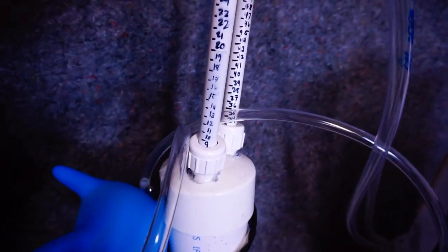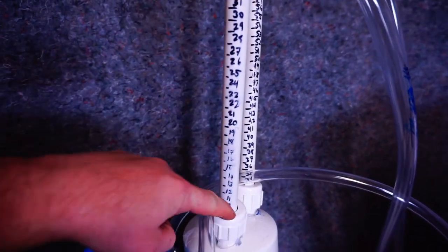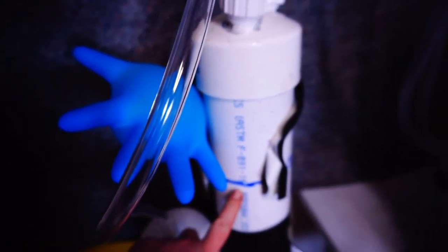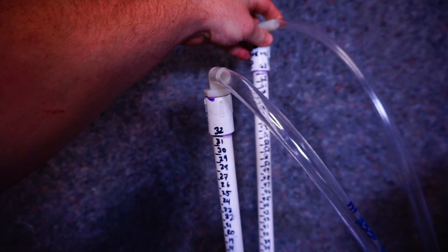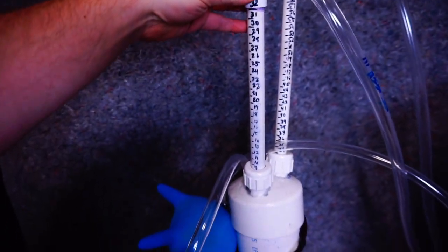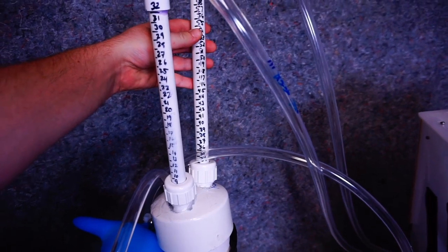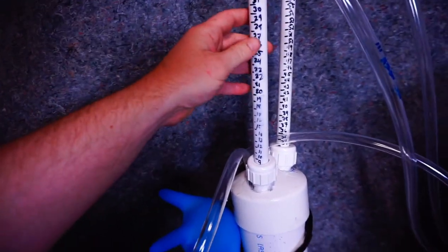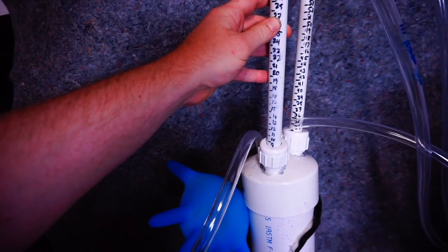You could also use PVC or nylon standard hose fittings that are cut to size, or again, in an industrial setting, you could injection mold them out of any sort of plastic material. So let's take a look at the machine. You can vary the PEEP pressure by changing the height of this tube. These numbers indicate the number of centimeters below the fluid line level that the end of the tube is sitting at, both for the overpressure tube and for the PEEP tube. And the overpressure tube is always on, and the PEEP is only on during the exhale part of the cycle.